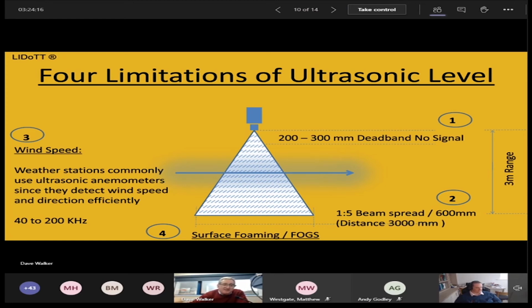Wind speed, as I've just mentioned: 40 to 200 kilohertz is used by the ultrasonic sensors for wind speed. So in large open environments where you've got wind passing through that beam, that will also create noise and interference on that ultrasonic sensor. And the final one on that slide is surface foaming, fogs, etc., fats, oils, and grease. They have a tendency to absorb the ultrasound and the energy. What we need is that energy hitting the actual target of measurement and returning back to the ultrasonic sensor in one go.